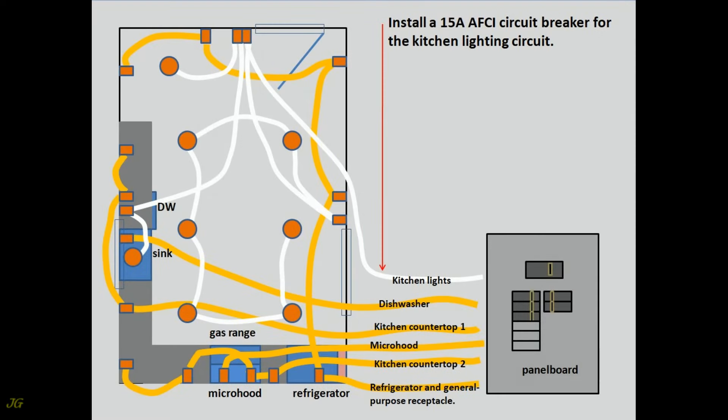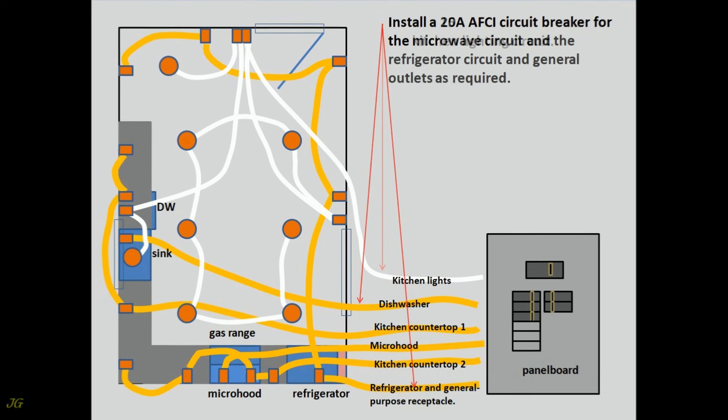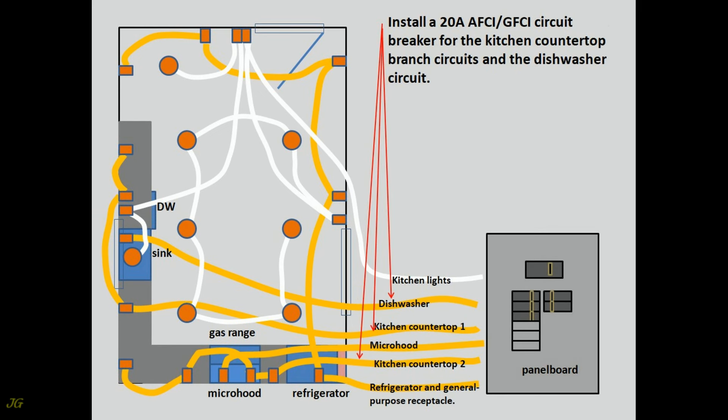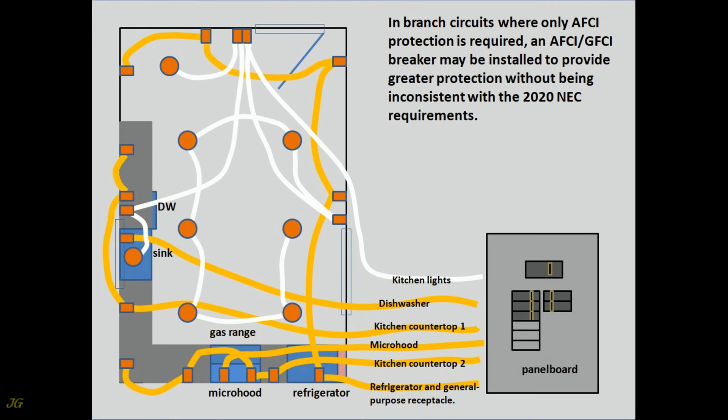Install a 15 amp AFCI circuit breaker for the kitchen lighting circuit. Install a 20 amp AFCI circuit breaker for the microwave circuit and the refrigerator circuit and general outlets as required. Install a 20 amp AFCI GFCI circuit breaker for the kitchen countertop branch circuits and the dishwasher circuit. In branch circuits where only AFCI protection is required, an AFCI GFCI breaker may be installed to provide greater protection without being inconsistent with the 2020 NEC requirements.